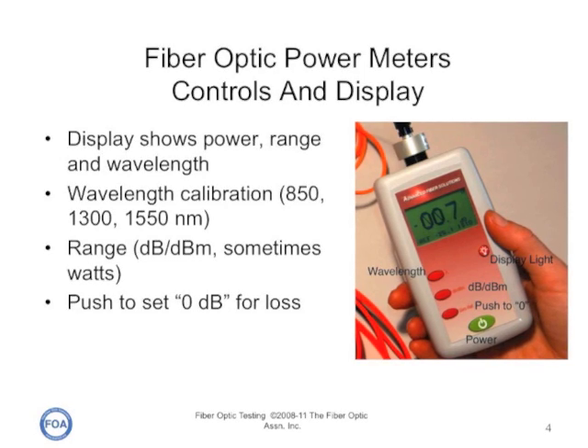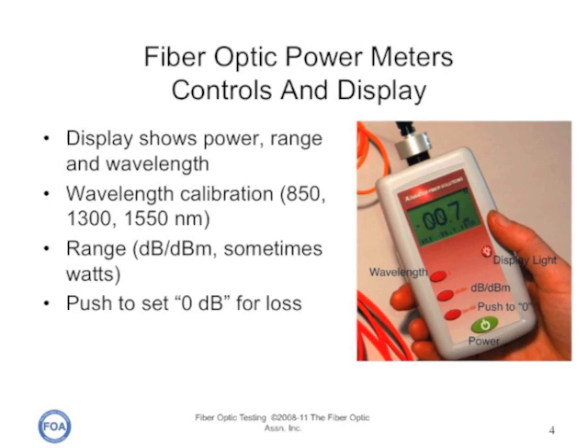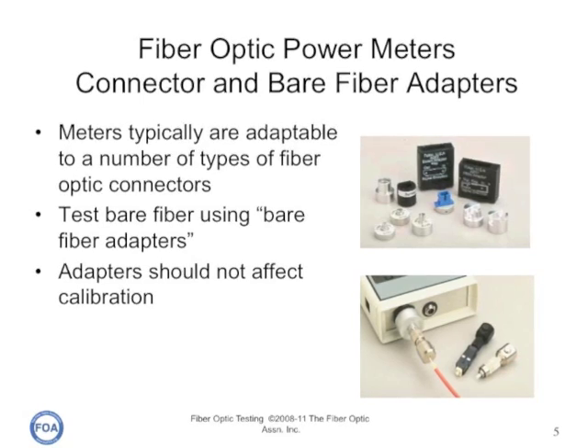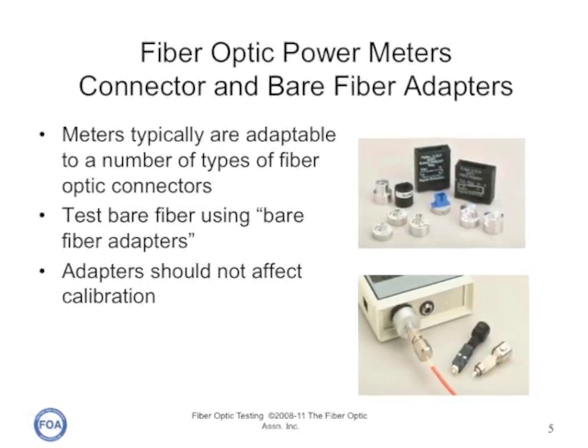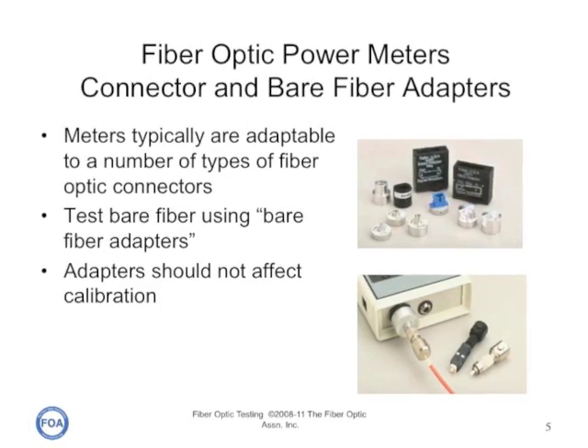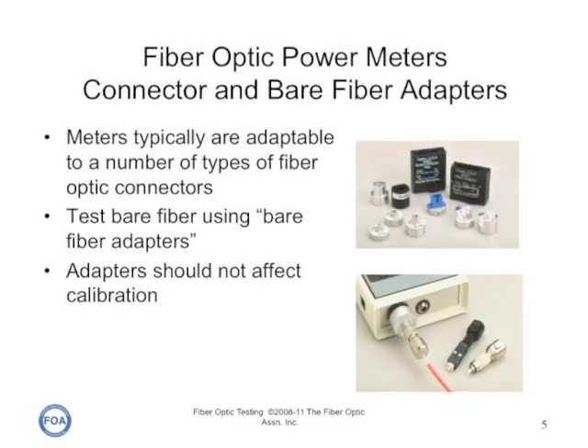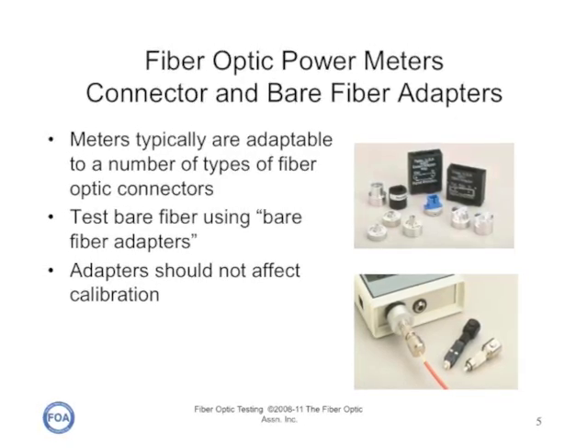Some meters have a push-to-zero to allow us to set a zero dB reference, though that's not calibrated — it's different for every measurement. Typically, fiber optic power meters are adaptable to a variety of different fiber optic connectors. At least a typical power meter will adapt to ST, SC, and LC fiber optic connectors.